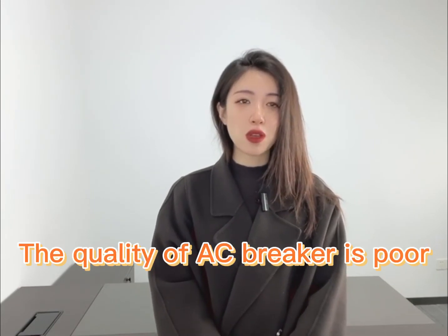The quality of the AC breaker is poor. The working temperature protection and fire protection grade shall be determined according to the operating environment. Generally, DC switches with good quality can work stably from -40 degrees Celsius to 60 degrees Celsius. The protection grade of a common external DC switch is IP65. After the installation of the built-in DC switch, the whole machine can pass IP65. Sometimes your AC breaker keeps tripping off, but you find that your photovoltaic system has no problems, and your AC breaker is hot, has a burning smell and looks damaged. It's likely that your AC breaker is of poor quality. Time to replace it.